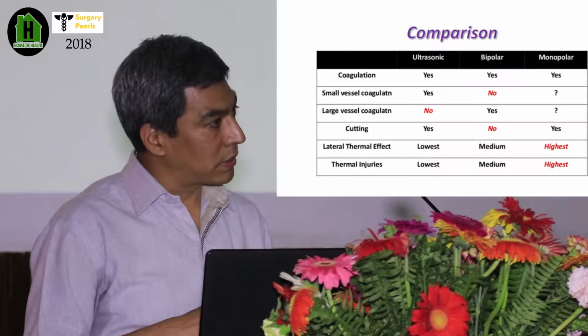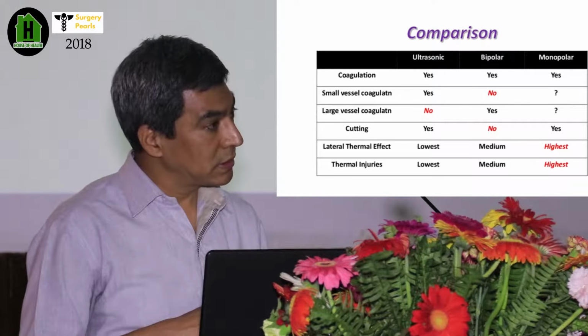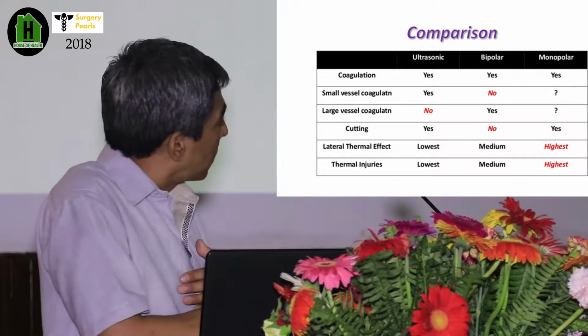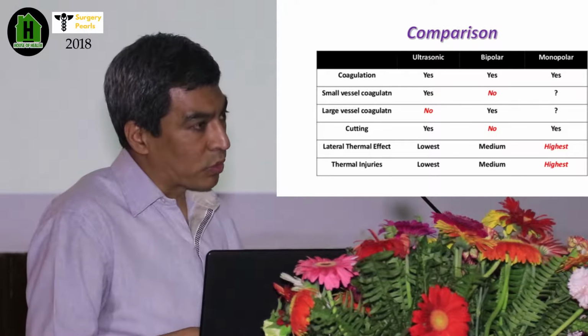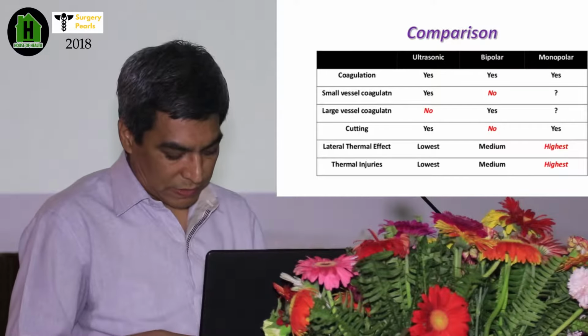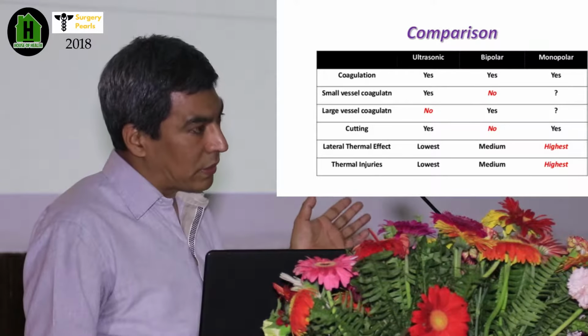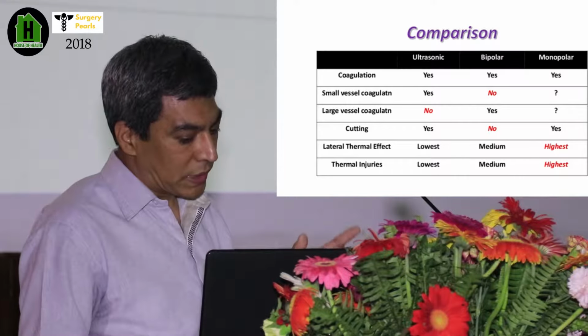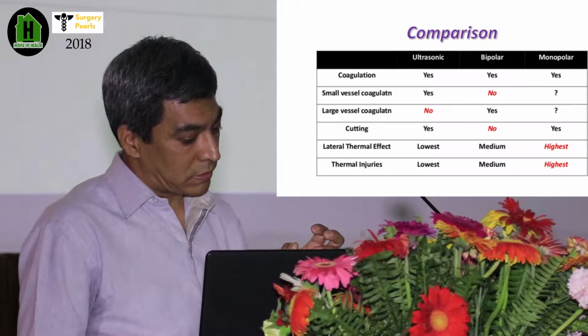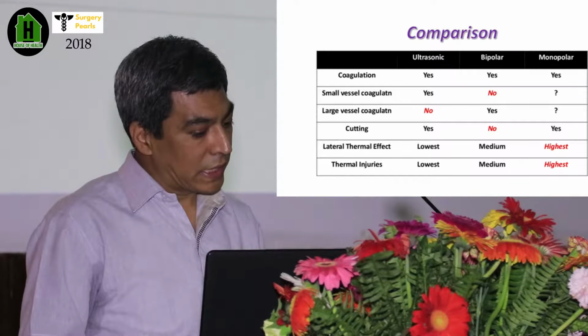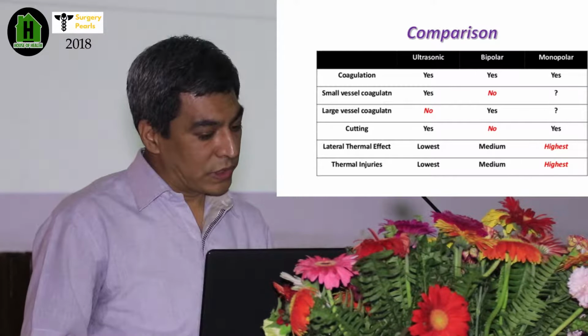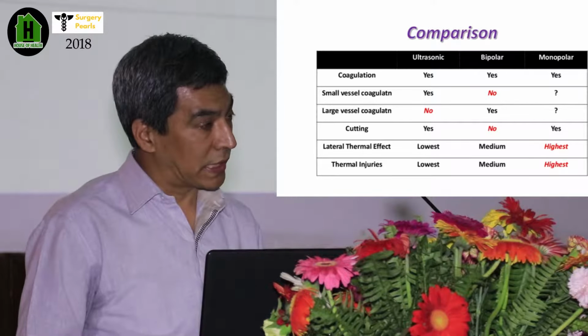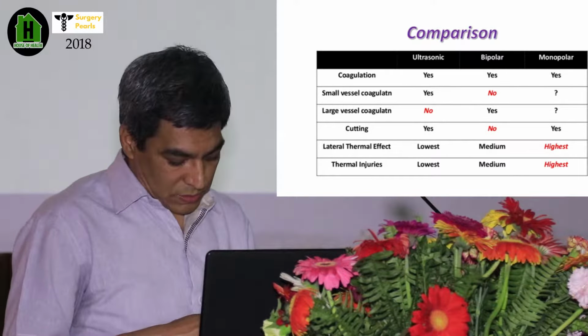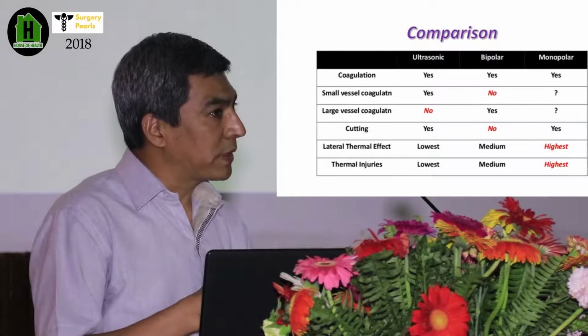If you compare ultrasonic devices with the other electrosurgical devices, the thermal spread is very low compared to the other two, monopolar and bipolar. This is the safety of these ultrasonic devices. Again, compared with monopolar and bipolar, the ultrasonic has a very low lateral thermal effect and gives very good cutting as well as vessel sealing. I'll just skip. Thunderbeat is one example of the ultrasonic devices that we use daily.